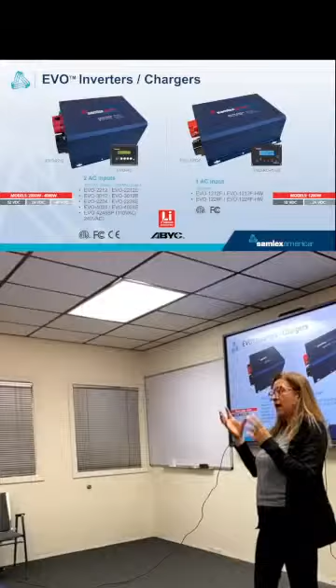It can work with any kind of lead acid battery, AGM or gel, and also lithium. Programming is performed through the Evo RC Plus remote. All the options can be programmed independently. You can choose the priority - maybe the photovoltaic, or maybe the grid, or maybe in a remote location you only have an alternator and a photovoltaic system, and the Evo starts the generator automatically. This avoids having to do anything manually.